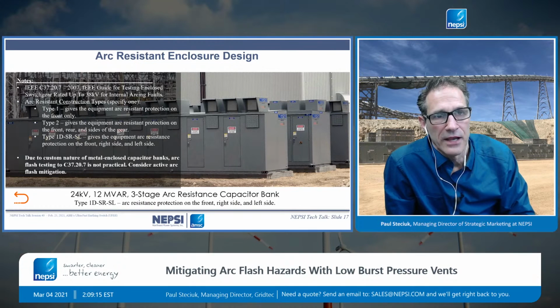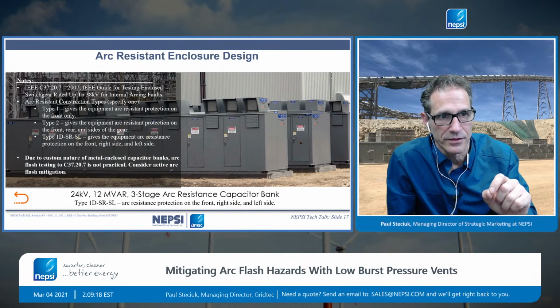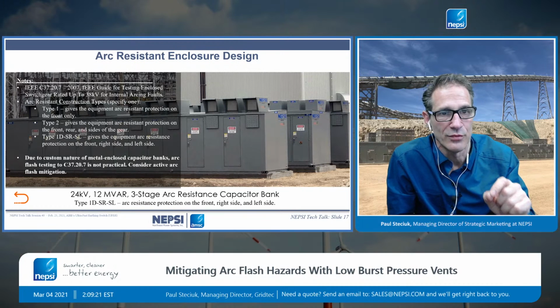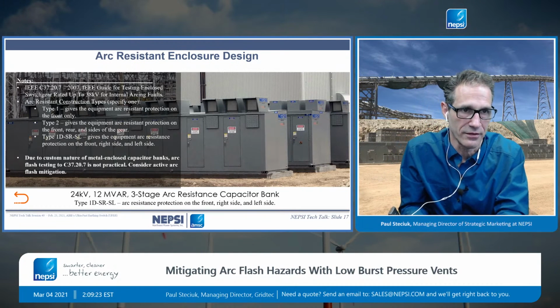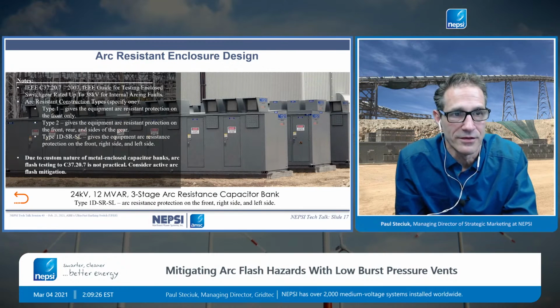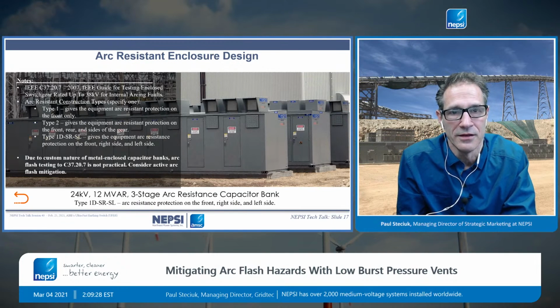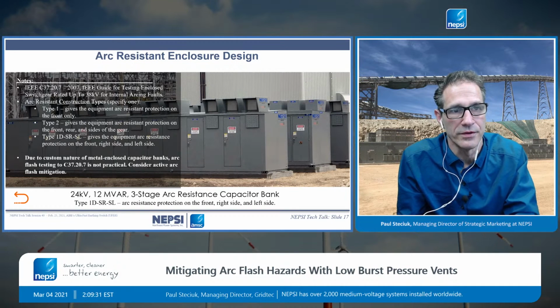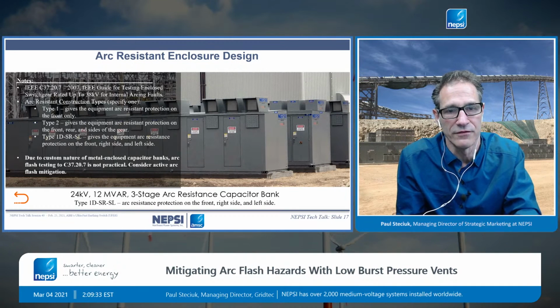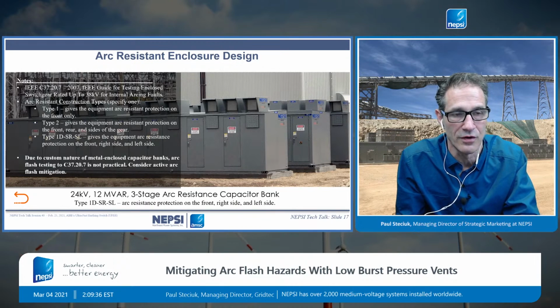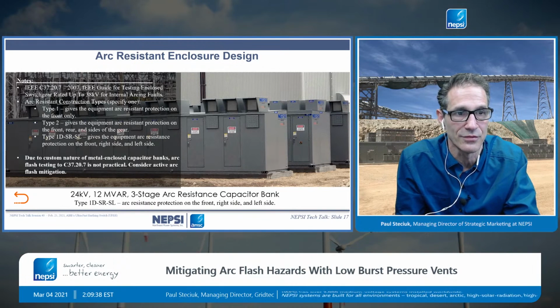The thing about this standard is if we want to certify the equipment for arc resistance, it means we have to send out the equipment to a testing lab, okay? And the reality is that we can't do that. We cannot build and design a custom piece of equipment, and every metal-enclosed cap bank and harmonic filter bank is custom. They are not standard off-the-shelf devices. Not like switchgear. Switchgear is almost off the shelf. You buy it, it's got a rating, it's got the same footprint each and every time. Our systems are different each and every time, depending upon the megavars of the system, depending upon the tuning points, and depending upon the switching device inside.